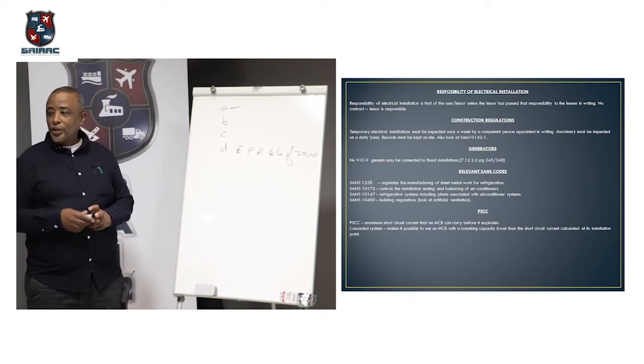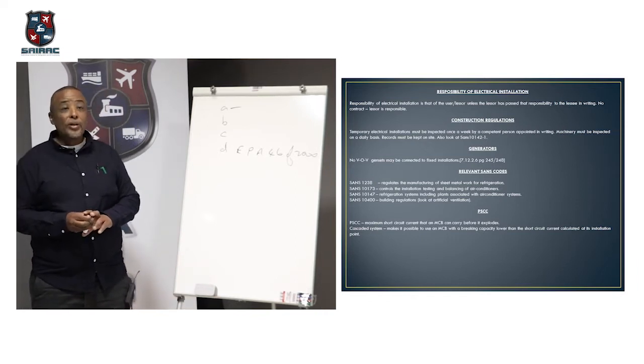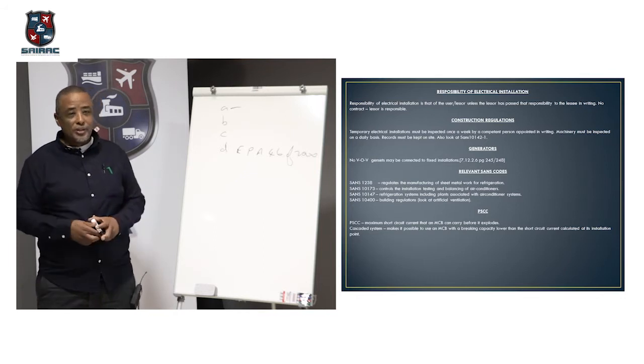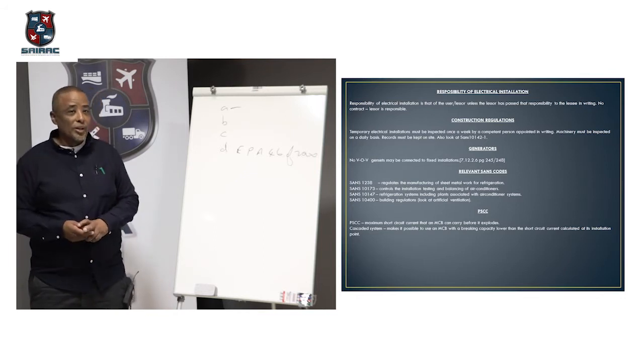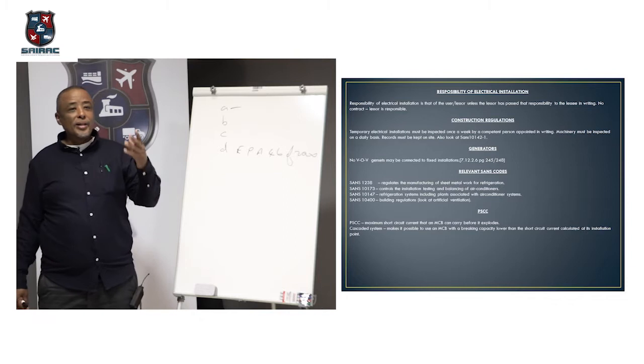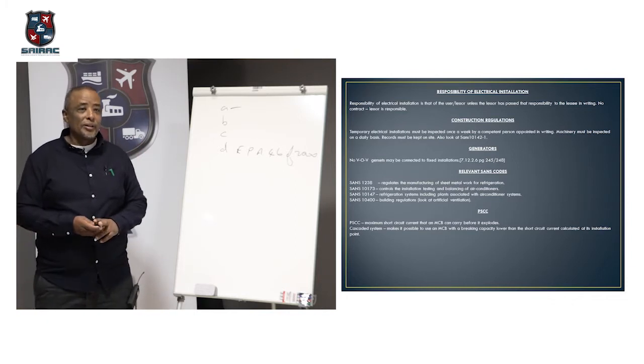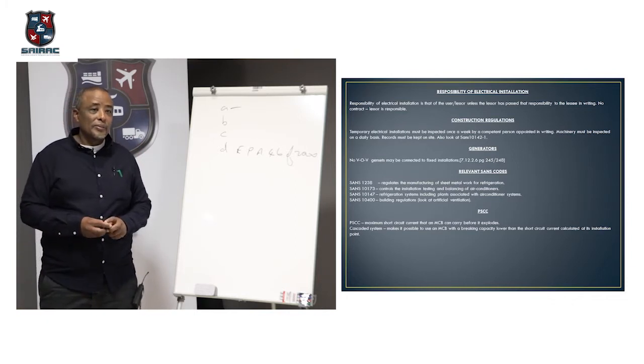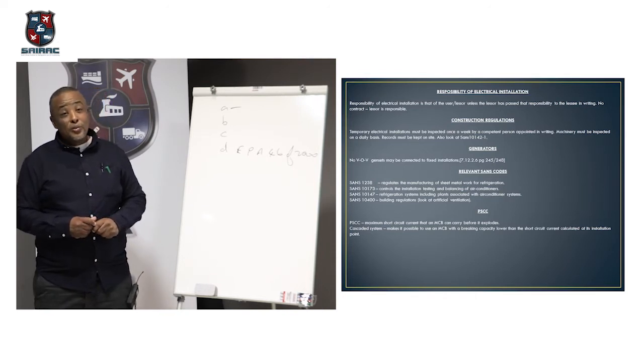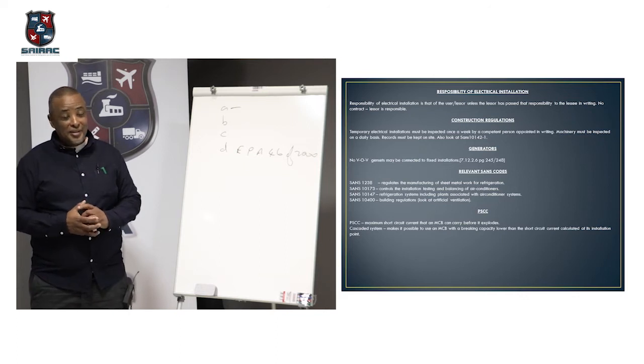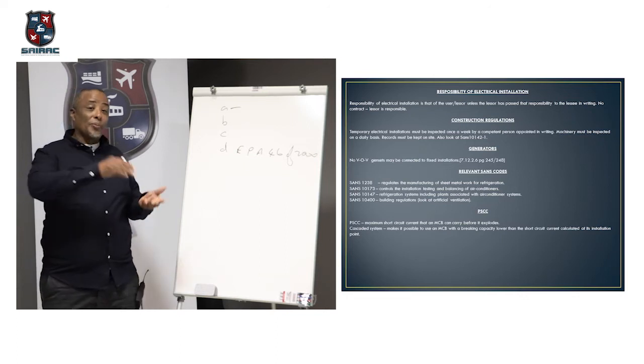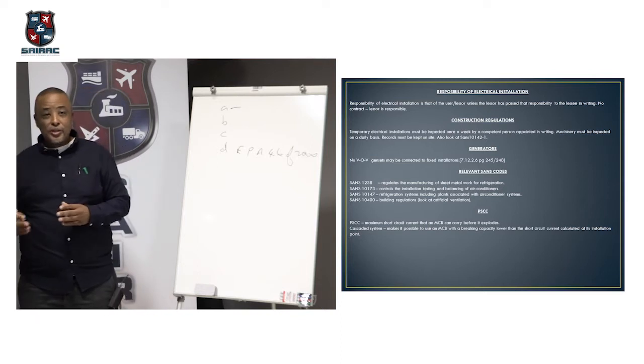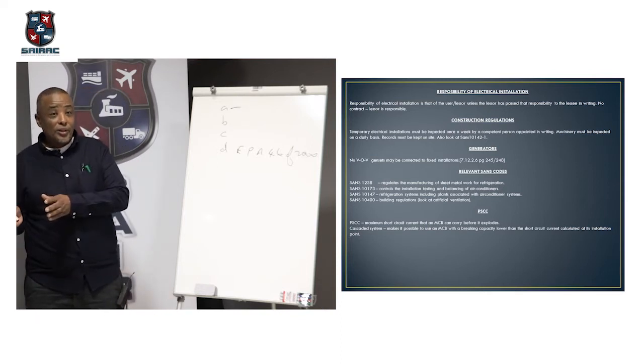If you've got less qualifications, less than N6, they will interview you and check your competency. Can you classify zones? Do you understand EXP, EXD, and those type of things? Because that's the other question. Your zone classification, where do I find that? Okay, classification of zones is something over and above a compliance certificate, the normal yellow compliance certificate that you've seen. There's an additional test report for hazardous areas and medical locations.